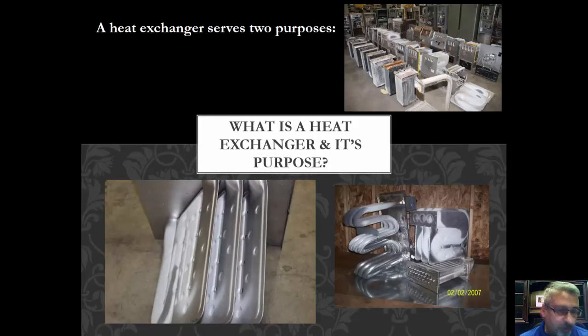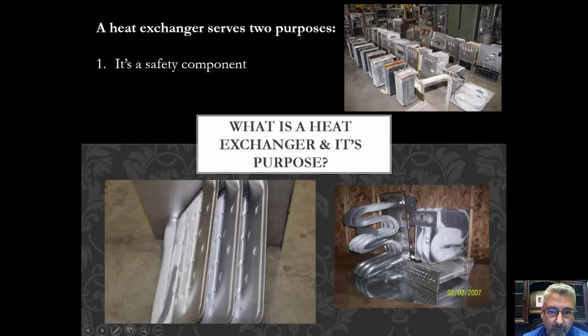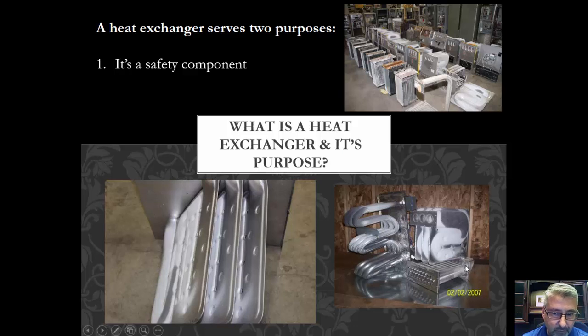A heat exchanger serves two purposes. Everybody thinks the heat exchanger is nothing more than the device that transfers heat — that is true — but it's also a safety component. It's a safety component because heat exchangers must be sealed. We can't have holes or leaks because we don't want flue gas inside a heat exchanger to enter the home. These are both from condensing gas furnaces. This one is a tubular heat exchanger, and this one is a serpentine that goes into a coupler box, into a secondary heat exchanger.